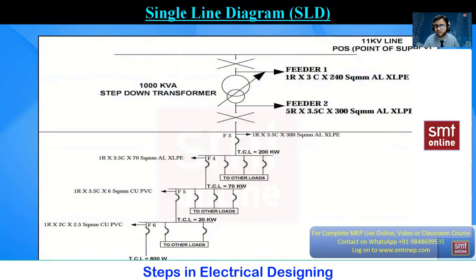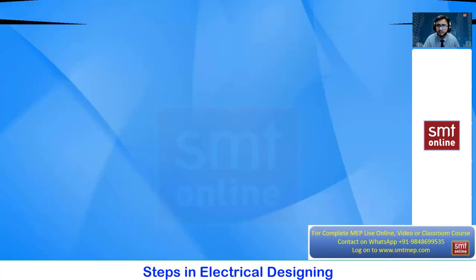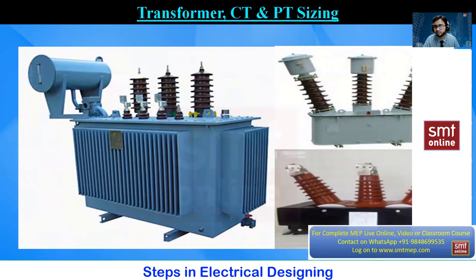A sample single line diagram with six feeders is shown. Feeder one is the point of supply, feeder two is the secondary side. For 200 kW of load, a 300 sq mm cable is proposed; for 70 kW, a 70 sq mm cable; for 20 kW, a 6 sq mm cable; and for 800 W on feeder six, a 2.5 sq mm cable. The single line diagram gives a complete outline and scope of the project.